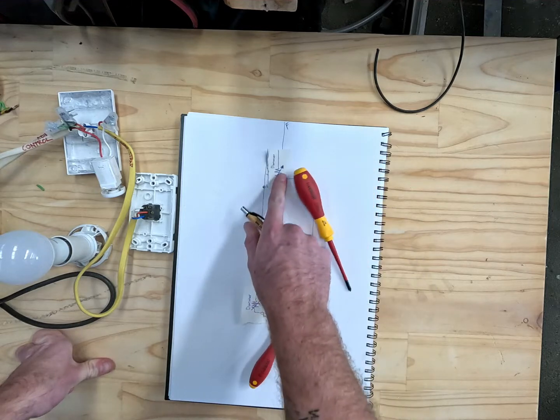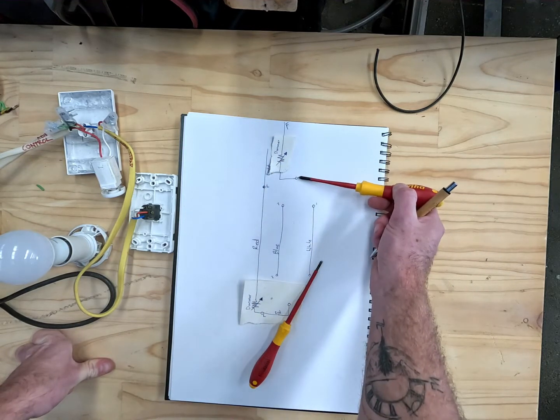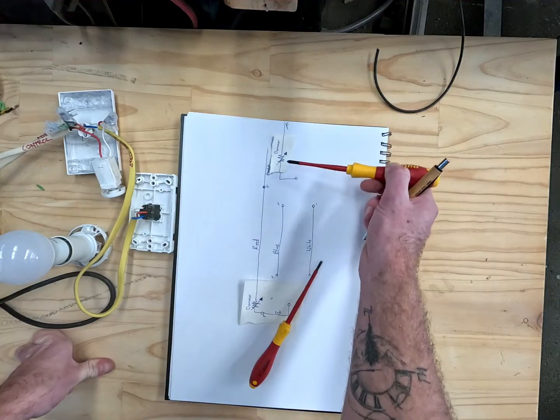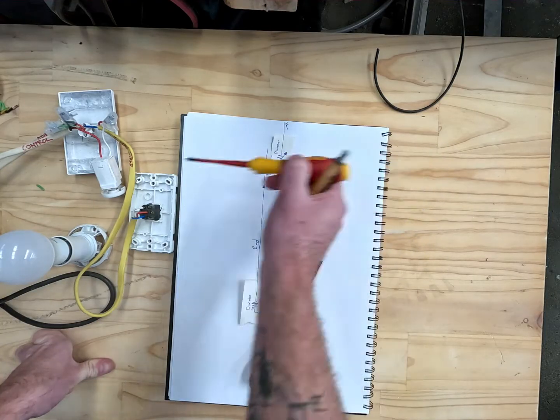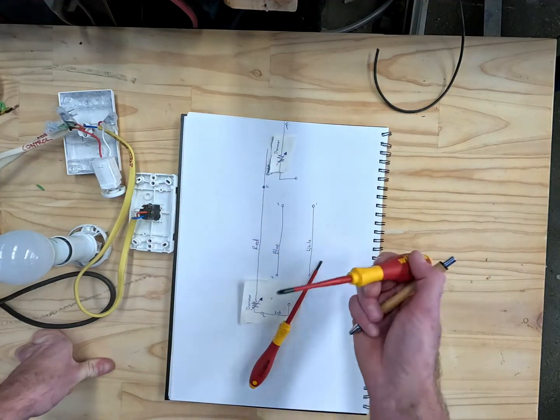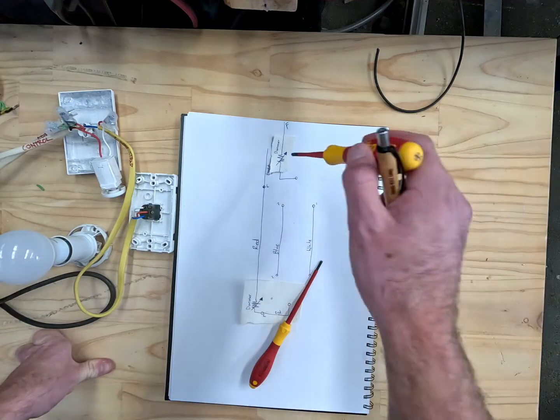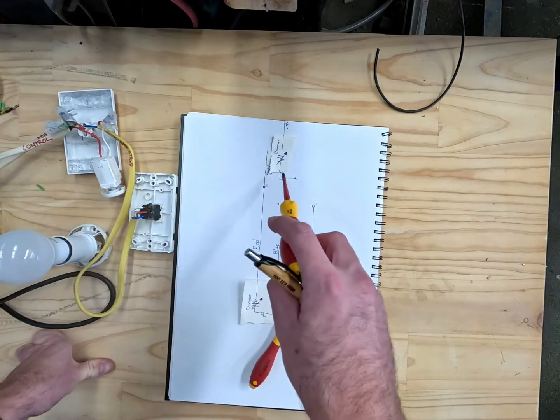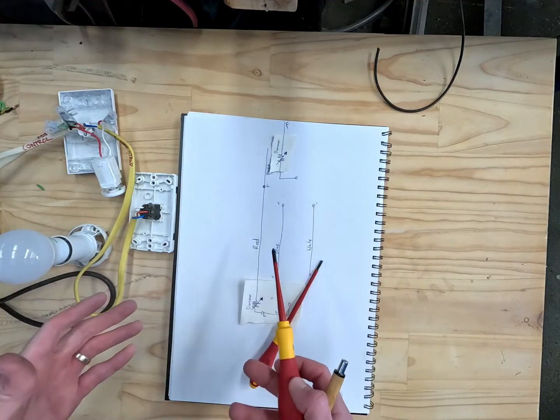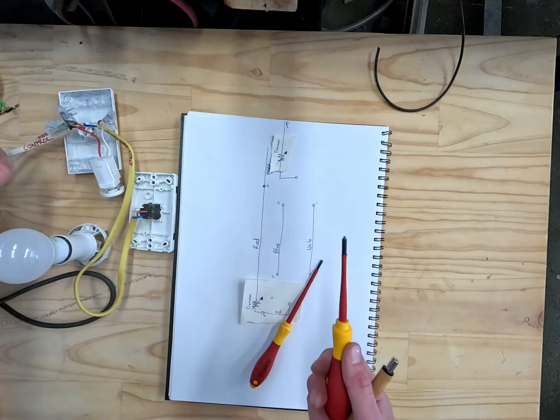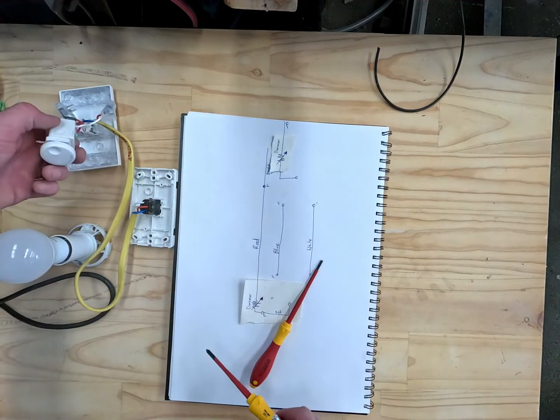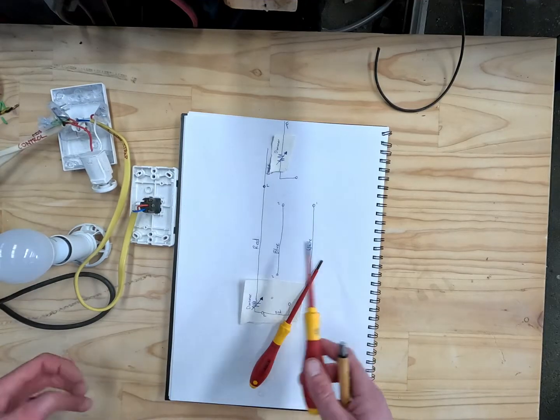So the third place that I was talking about is you could put it here, but as you can see, because you're above the light switch, you'll never actually turn the dimmer off, which won't hurt the dimmer. But somebody might go to open up the light switch and find that they disconnect the dimmer thinking it's dead. Not everybody tests all the time. They'll get a shock because it's live all of the time, which you don't want.